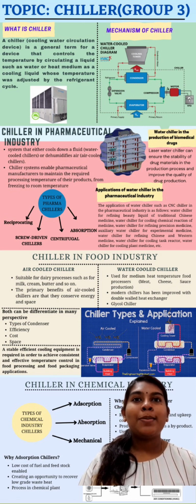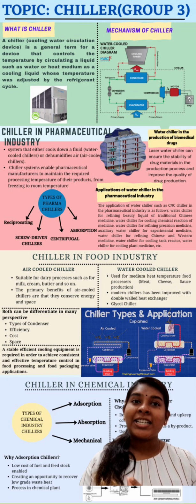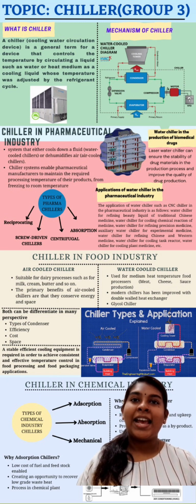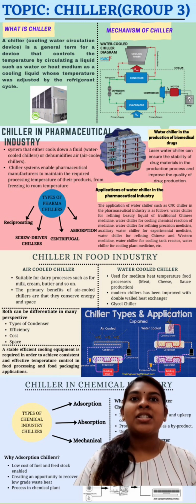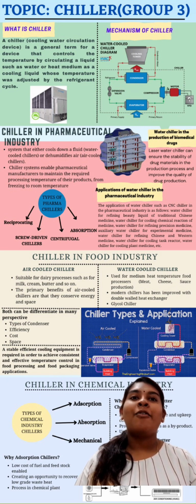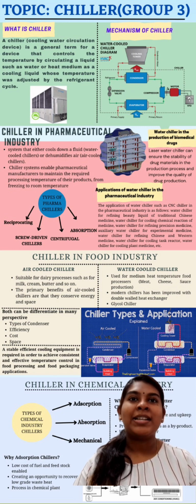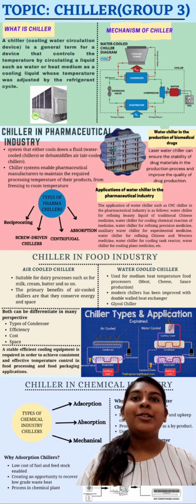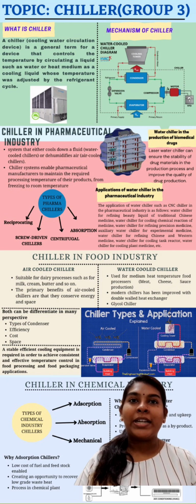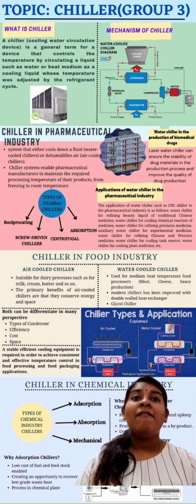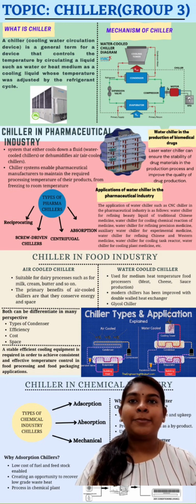There are two types of chiller, that is air-cooled chiller and water-cooled chiller unit, as it depends on the application and specific requirement of an industry. An air-cooled chiller has a condenser that is cooled by environment air. Meanwhile, water-cooled chillers have a water-cooled condenser connected to a cooling tower and are typically used in medium and large installations where there is an excess of water.